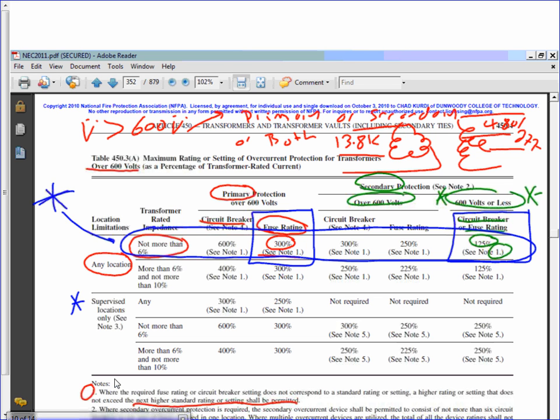I want to bring to your attention, guys, note number 1 here and here. What does note number 1 say? If you don't hit the standard, what do you do? You go up on the primary side. On the secondary side, guys, if your secondary is 600 volt or less, exactly like mine here, you're going to use 125. And do you see a note number 1 too? Yep. So what do you do with note number 1? You go up.